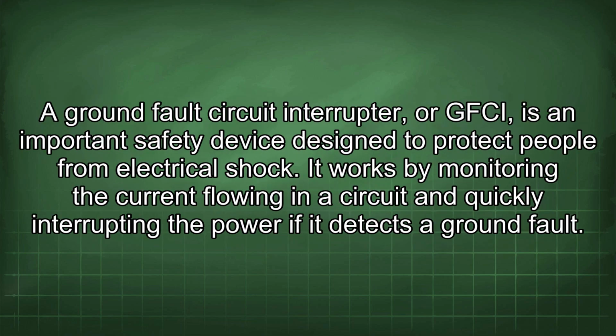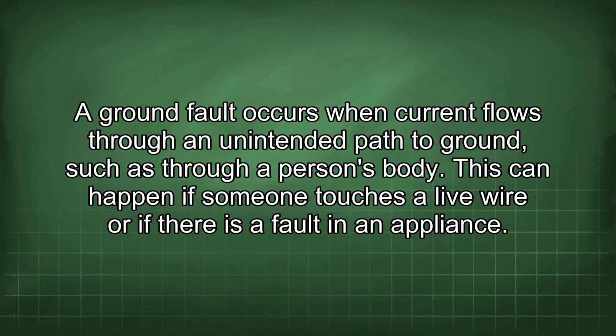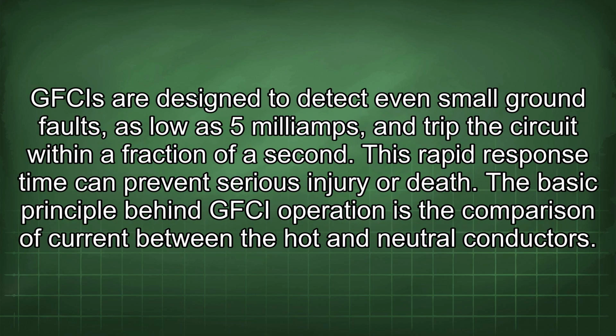A ground fault circuit interrupter, or GFCI, is an important safety device designed to protect people from electrical shock. It works by monitoring the current flowing in a circuit and quickly interrupting the power if it detects a ground fault. A ground fault occurs when current flows through an unintended path to ground, such as through a person's body. This can happen if someone touches a live wire or if there is a fault in an appliance. GFCIs are designed to detect even small ground faults as low as 5 mA and trip the circuit within a fraction of a second. This rapid response time can prevent serious injury or death.